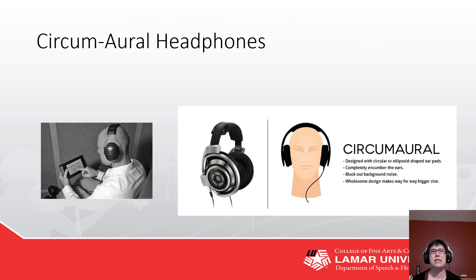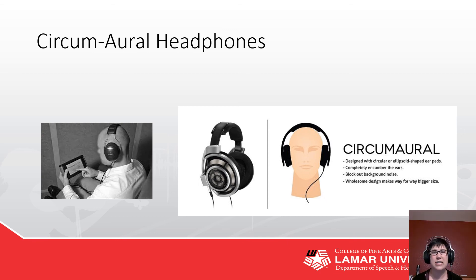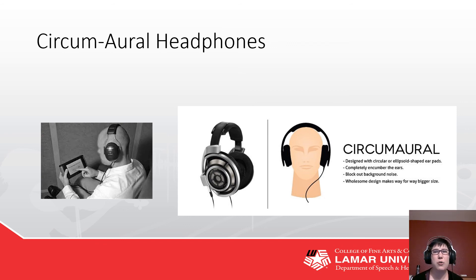The next type is circumaural headphones — the kind I'm wearing right now — and they go all the way around and completely encase the pinna. You'll most often see these with extended or high frequency testing. They don't press down and compress the pinna, they're much less likely to have sound escaping, they're more comfortable to most people, and they block out more background noise.